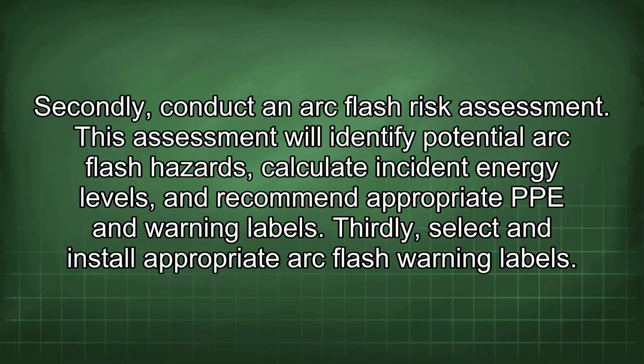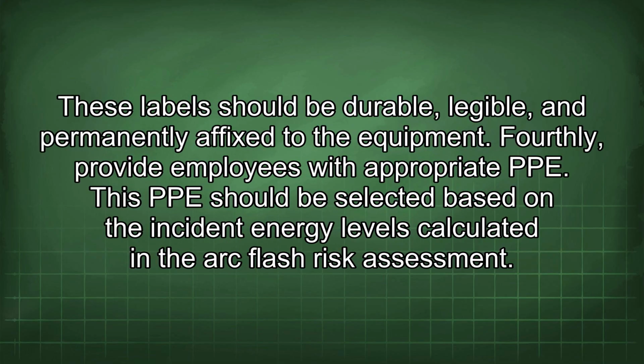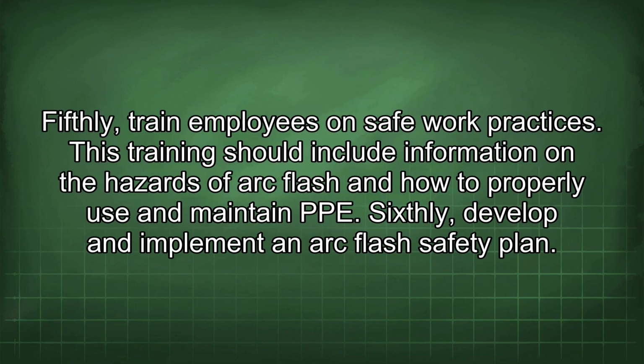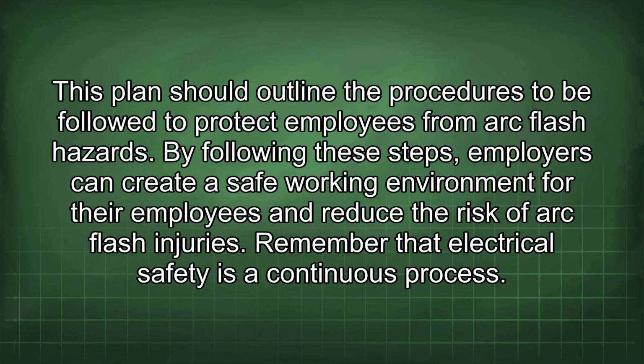Thirdly, select and install appropriate arc flash warning labels. These labels should be durable, legible, and permanently affixed to the equipment. Fourthly, provide employees with appropriate PPE. This PPE should be selected based on the incident energy levels calculated in the arc flash risk assessment. Fifthly, train employees on safe work practices. This training should include information on the hazards of arc flash and how to properly use and maintain PPE. Sixthly, develop and implement an arc flash safety plan. This plan should outline the procedures to be followed to protect employees from arc flash hazards.